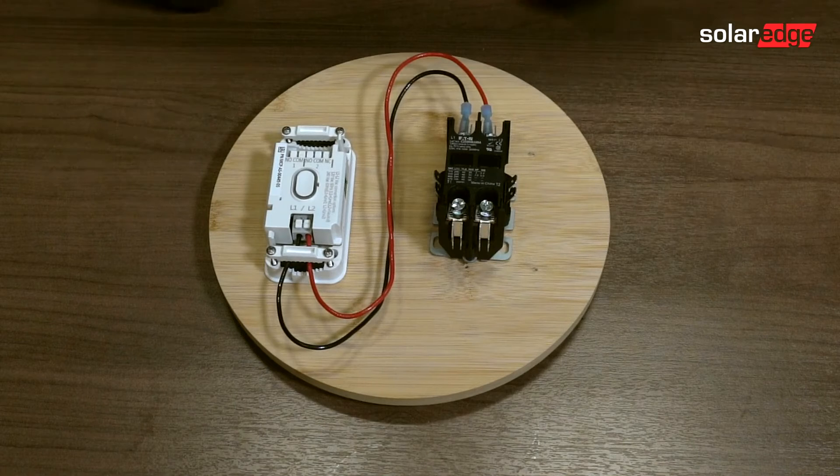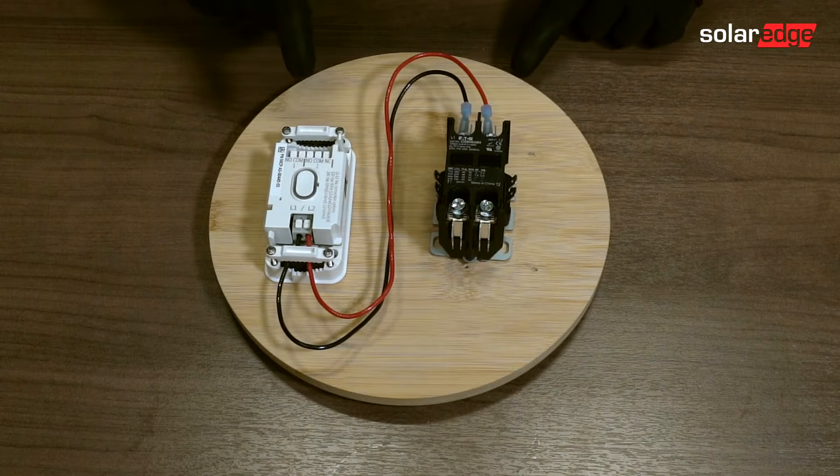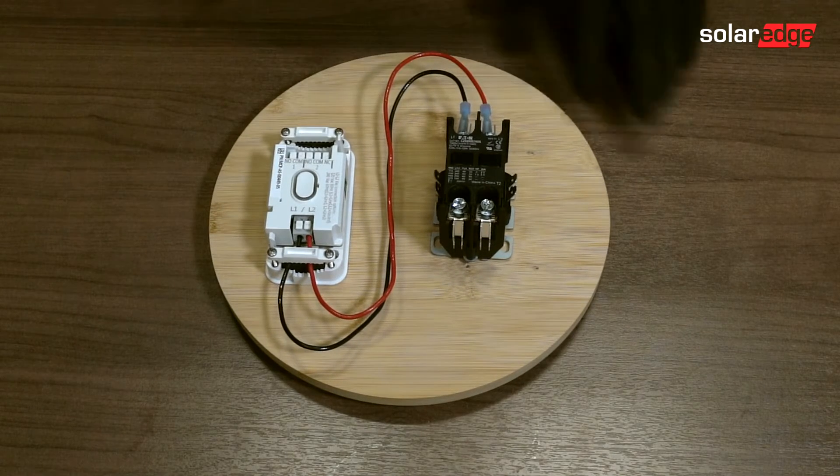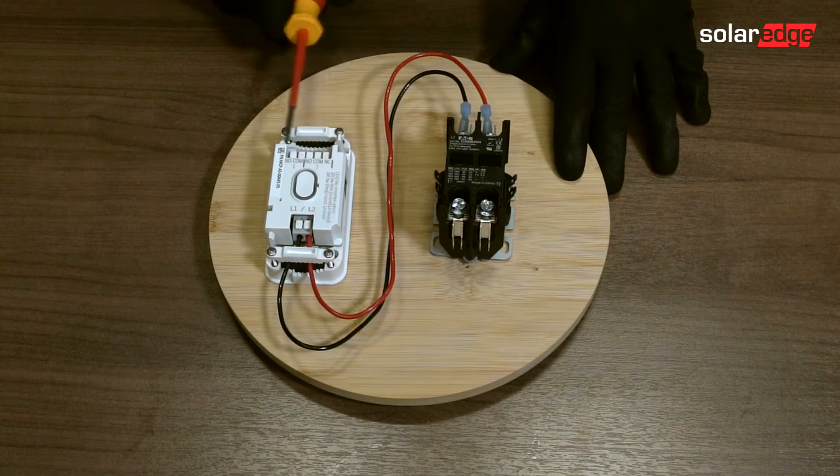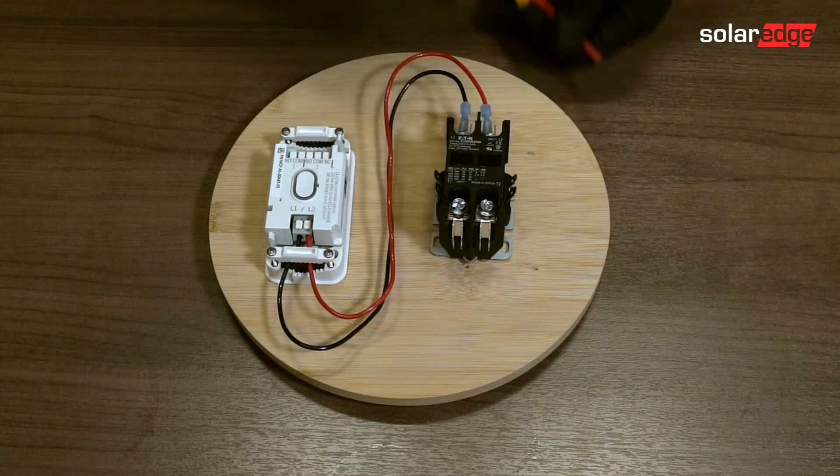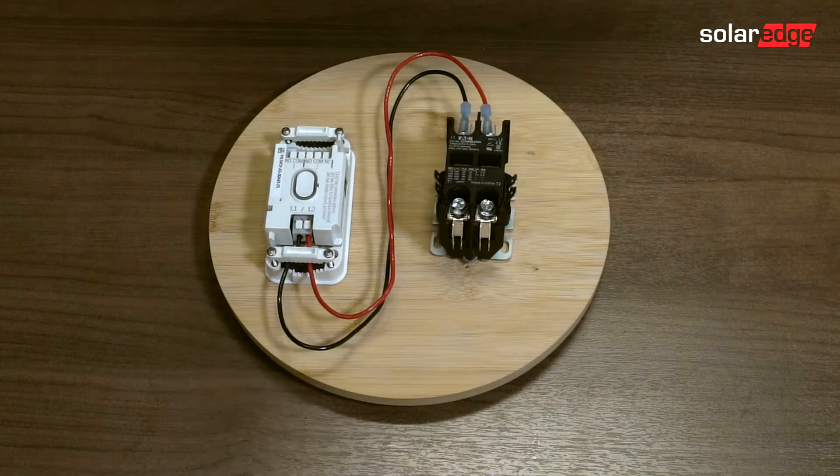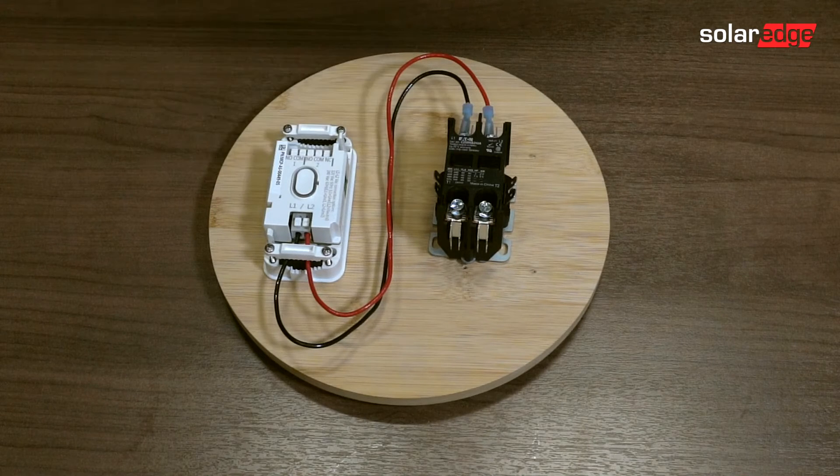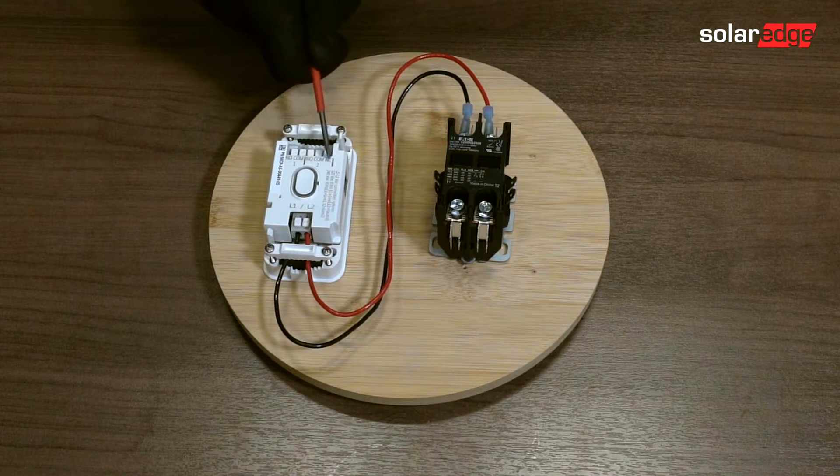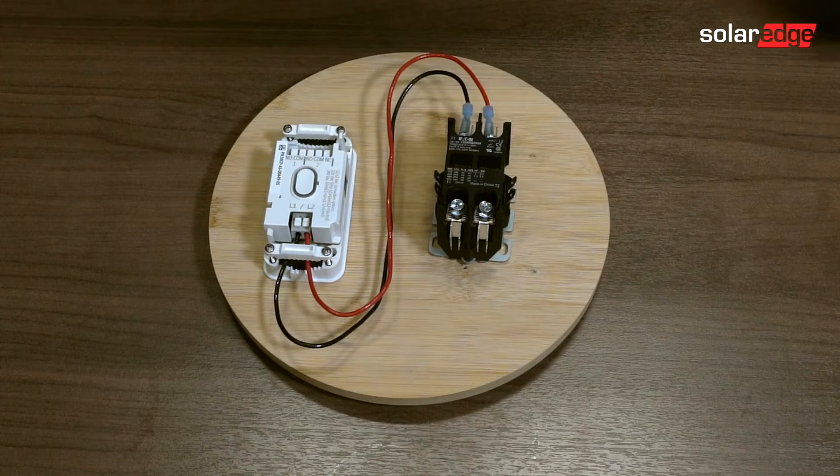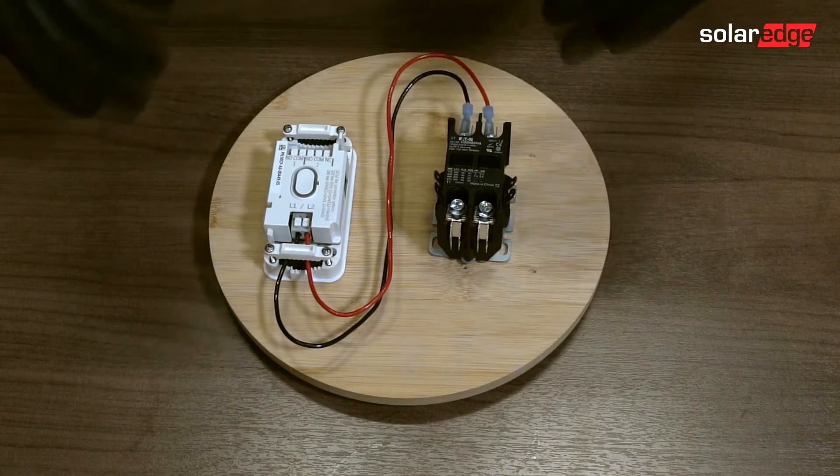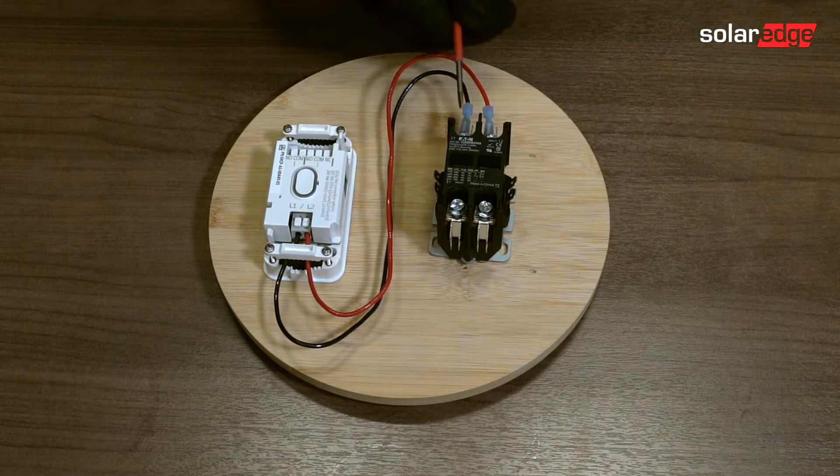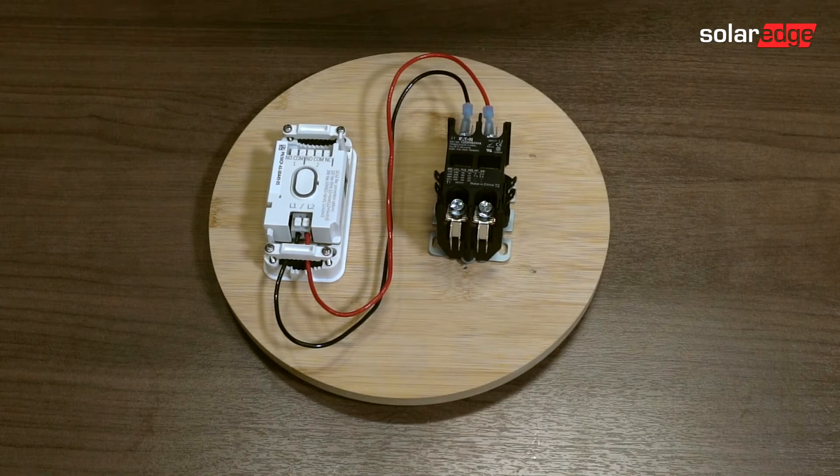Now we're going to wire our control. The common is going to be connected to line one and the normally open or the normally closed positions are going to be connected to the coil, and that's what controls the coil. So now we're going to wire the control side of the load controller to the contactor. The normally open or normally closed positions are going to be wired to the coil, and that's the state of the coil. Is it on or is it off? Is it open or closed? And the common is going to be wired as a voltage reference and is going to be wired to the supply side of the load controller.